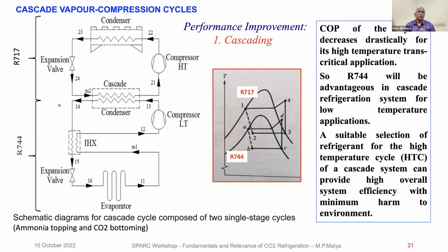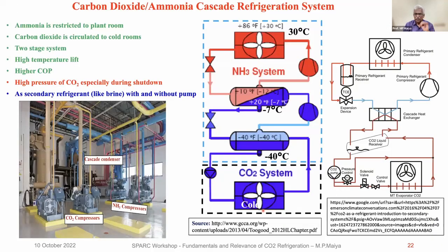Okay, so your ammonia evaporator is at minus 10, and the CO2 condenser at minus 5. So there is a 5 degrees centigrade difference for heat transfer. Your CO2 system will operate subcritical, and of course ammonia is subcritical. So your efficiency will improve. That is one way of doing it, and probably you can read this yourself. And I think Professor Ram Gopal gave the natural circulation loop.